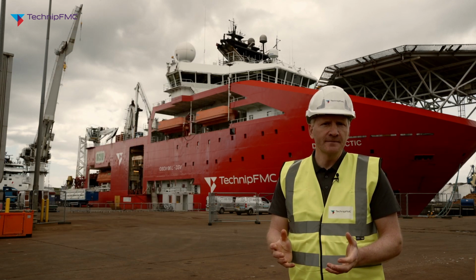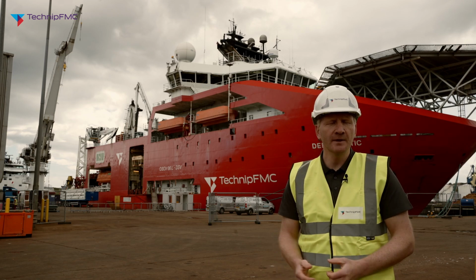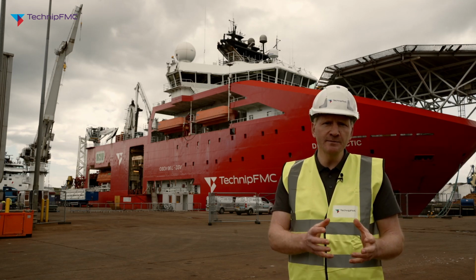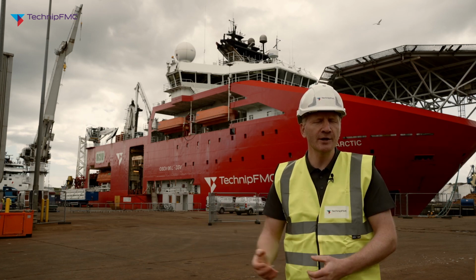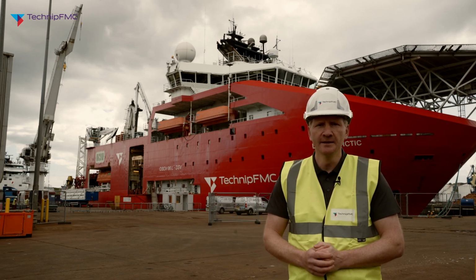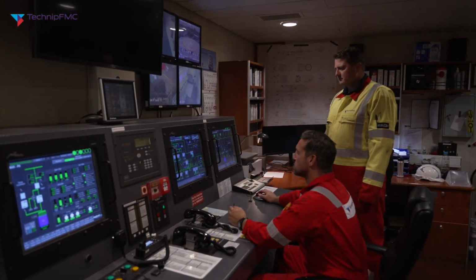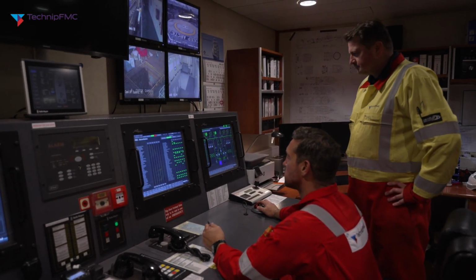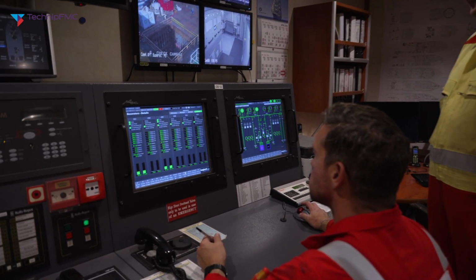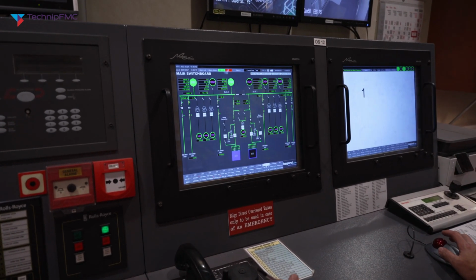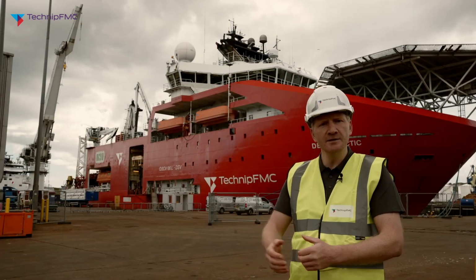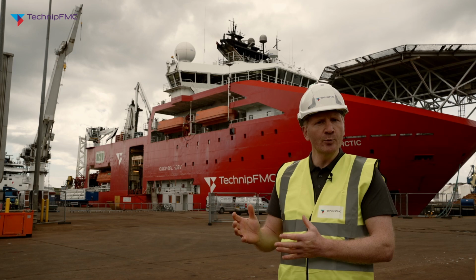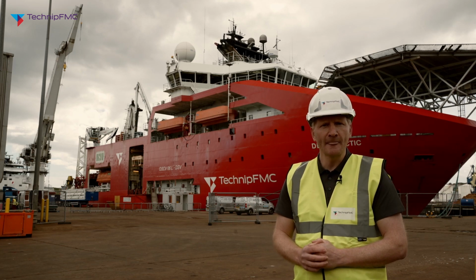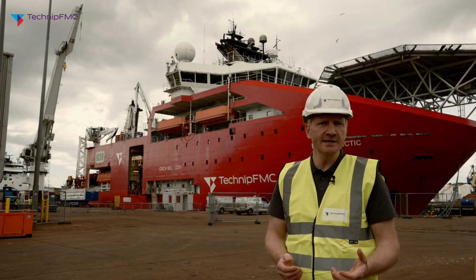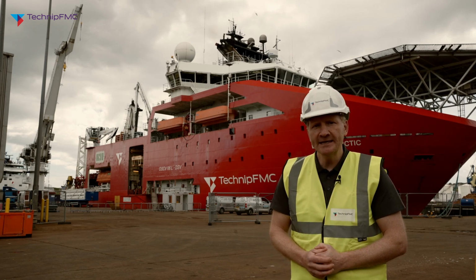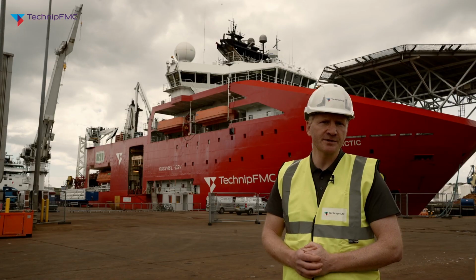On the control side, we have a number of things to do with interfacing. We need to ensure the battery management system is communicating with the vessel power management system to make sure we have that power on demand when we need it. We need to make sure the engineers can monitor the state of health of the batteries and all the other systems we mentioned, from the engine control room, so we have to interface all of that with the integrated automation system, or IAS. Finally, we need to make sure the DP operator, the dynamic positioning operator on the bridge, has information at all times on the state of health and state of charge of the batteries, in case he needs to give the command to start standby engines.